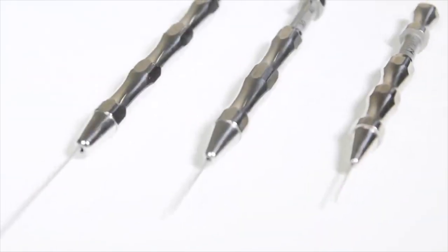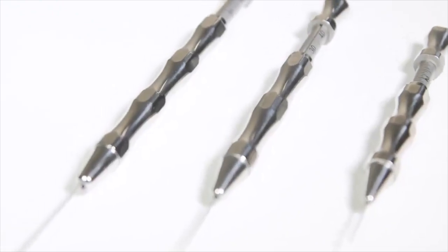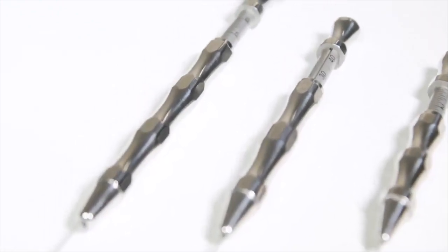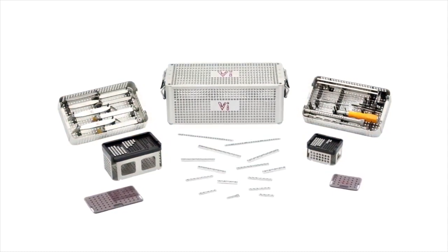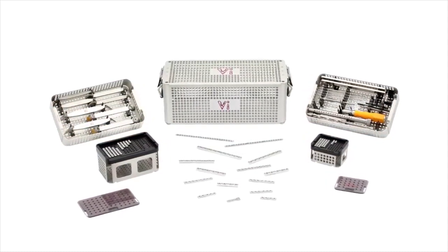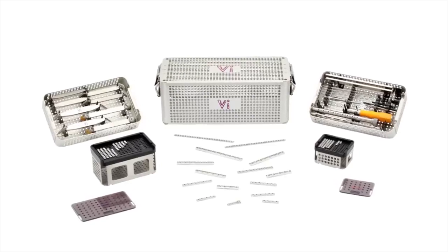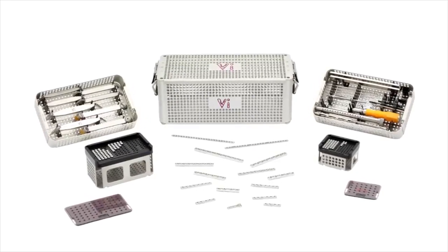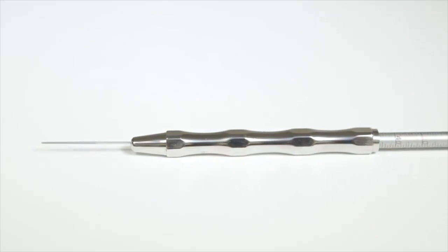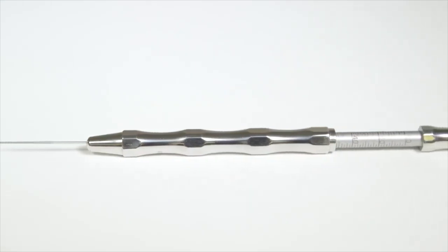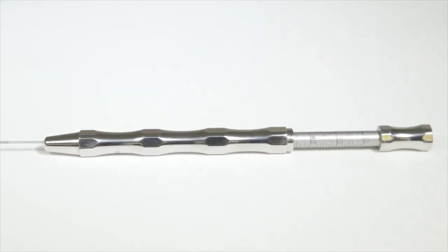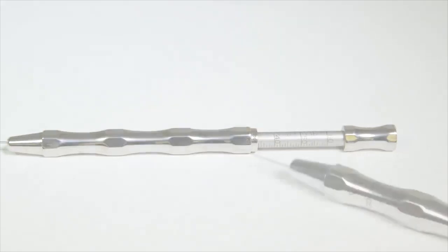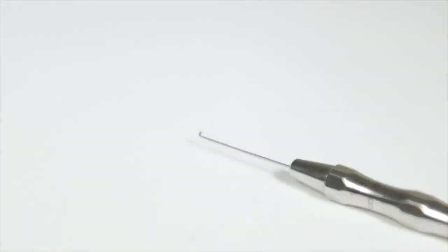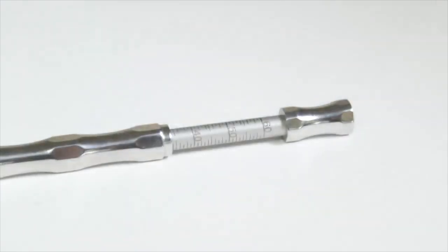These devices are size-specific, according to the size of implant being used. Cortical plating kits are supplied with the appropriate size depth gauge as a standard component of the kit, but they are also available separately. When the pilot hole has been drilled, the surgeon will measure the depth of the hole using the depth gauge. The depth gauge has a slender probe with a fine hook and a scale on the movable section of the device.